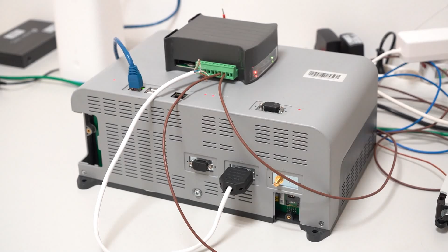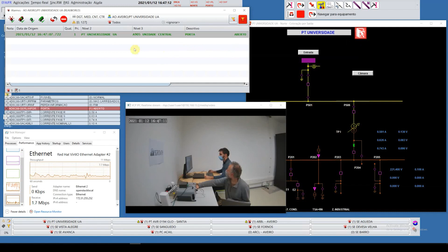This enhanced supervision of the secondary substation would not be possible with the communication technology currently deployed in the distribution network across the secondary substations. We are talking most commonly about GPRS, with very low throughput capabilities and higher latency than required for real-time remote operation. We can see in the operator interface that we have good quality video streaming from inside the substation. At the same time, the telemetry from the electrical network and from that substation in particular, continue to arrive to the control center in real time. The operator can accept this alarm or any other, and in the event of new abnormal occurrences in the network they will continue to arrive to the control center and show up in the operator interface.